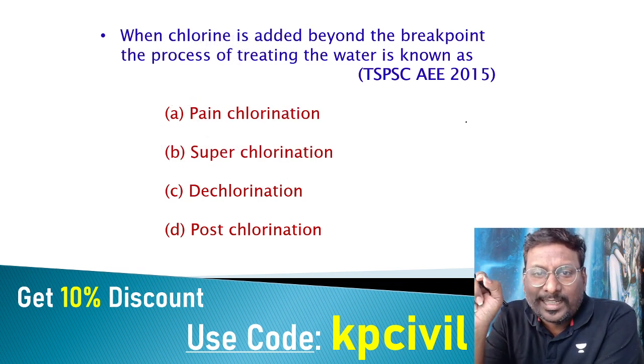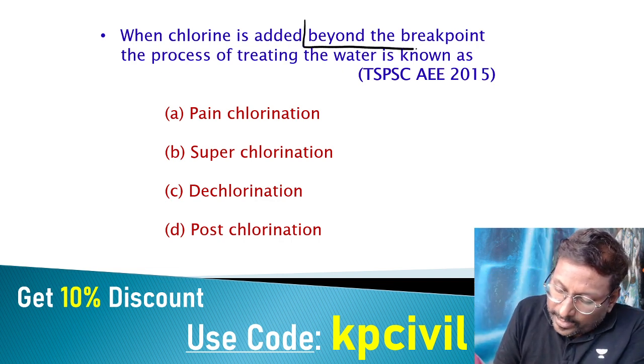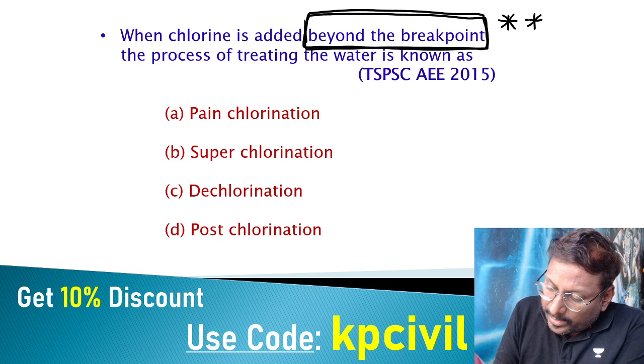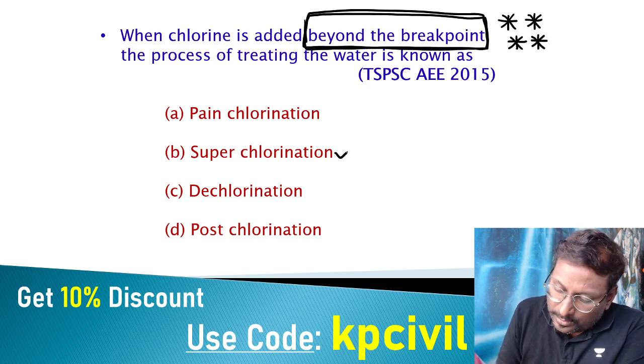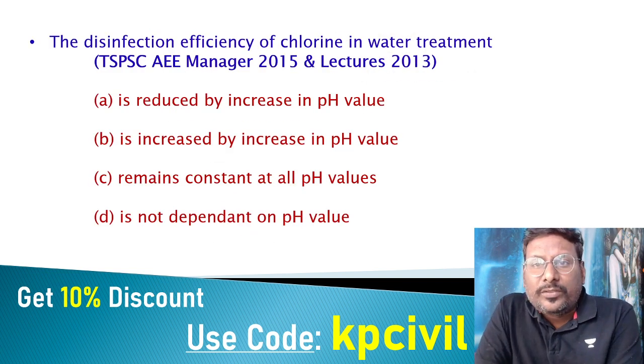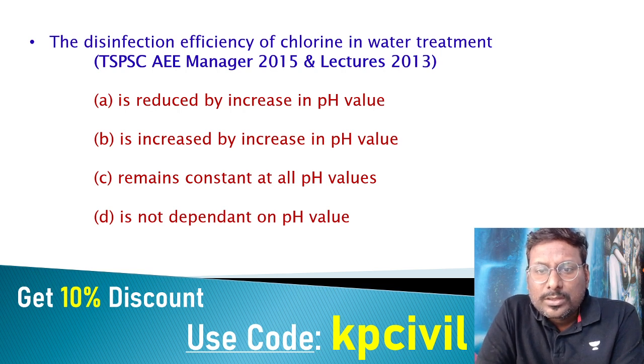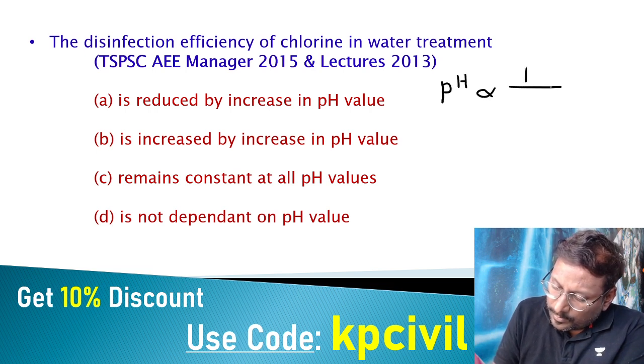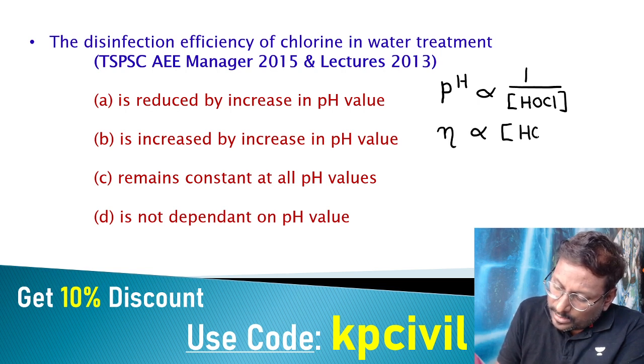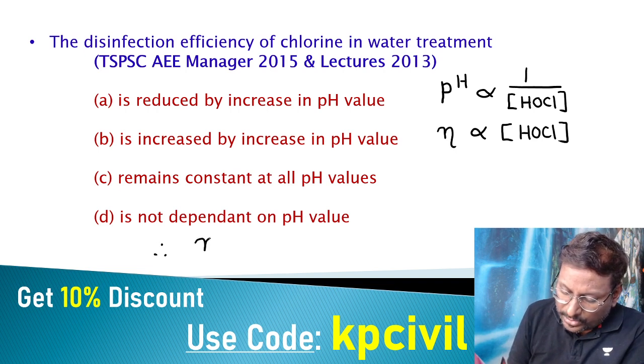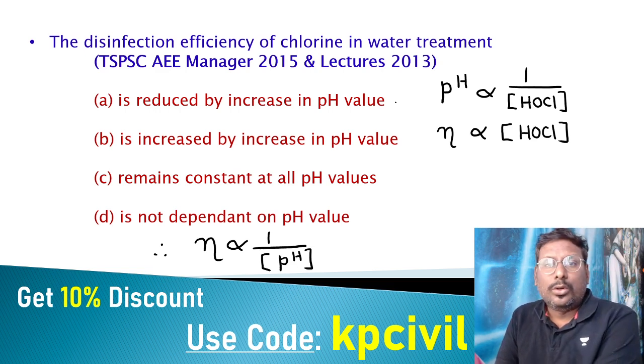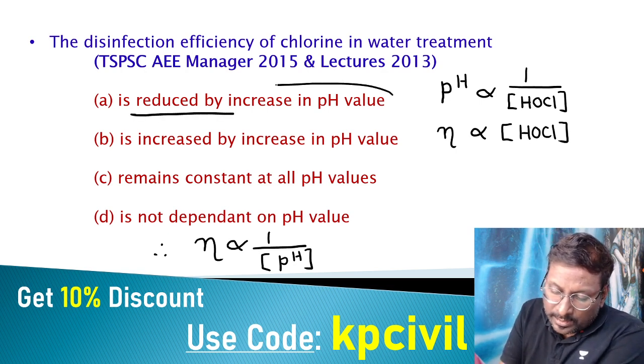When chlorine is added beyond the breakpoint, the process of treating water is called super chlorination — this is very important and frequently asked. Put a star mark on it. Disinfection efficiency of chlorine with respect to pH: as pH of water increases, concentration of HOCl decreases, and since efficiency is directly proportional to HOCl, efficiency decreases with increasing pH. So disinfection efficiency is reduced by increased pH value.